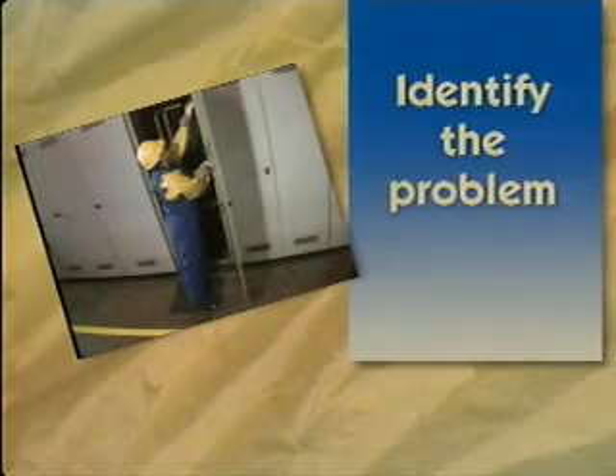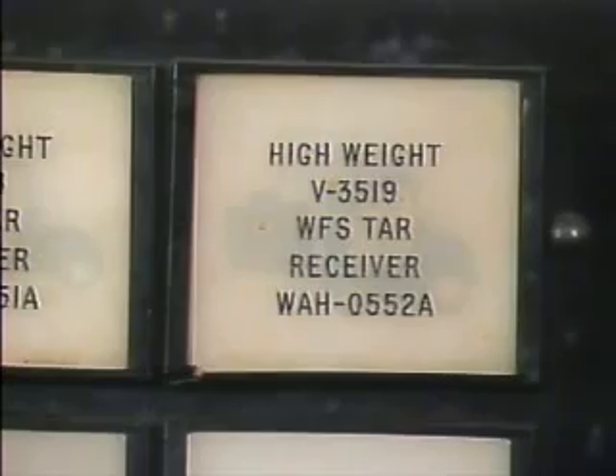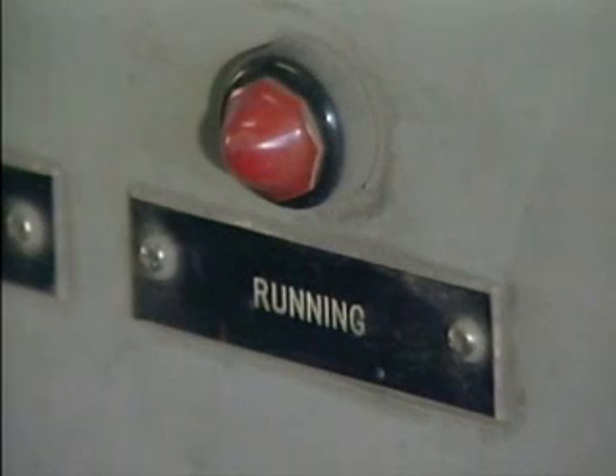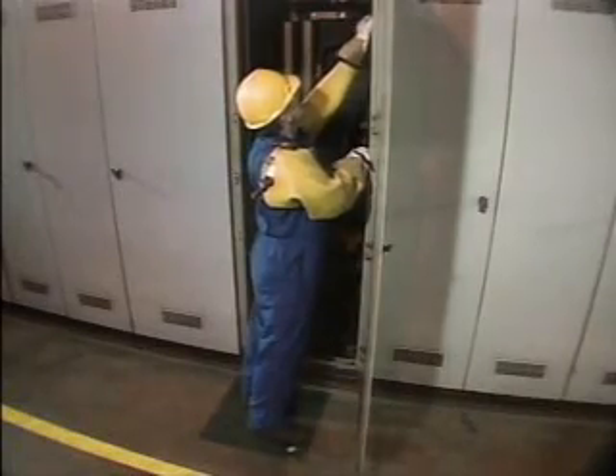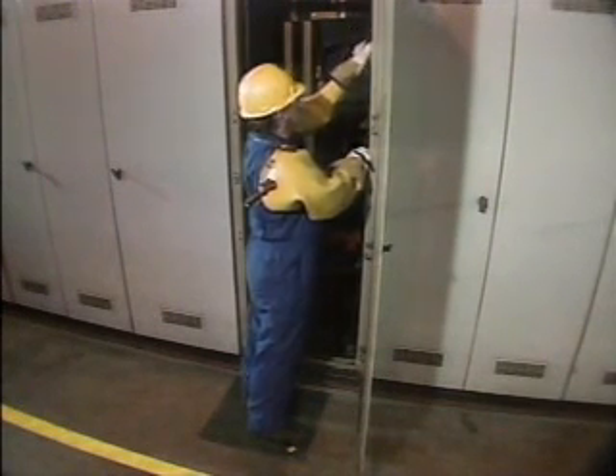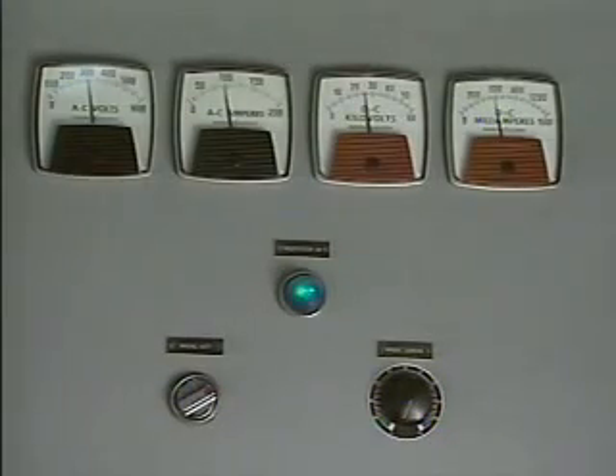The first step of our procedure, identifying the problem, includes recognizing that a problem exists and observing its symptoms. To perform this step, an electrician can use many sources of information. Alarms and annunciators can give visual or audible warnings of possible abnormal conditions. An automatic shutdown can also indicate a problem. In addition, a routine inspection could reveal a problem. Another sign that may indicate a problem is a signal value that is not within its normal range.